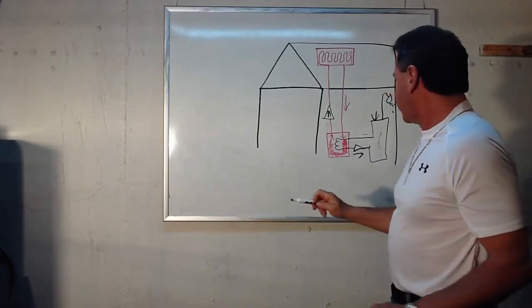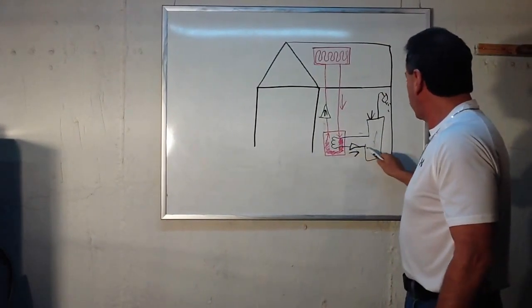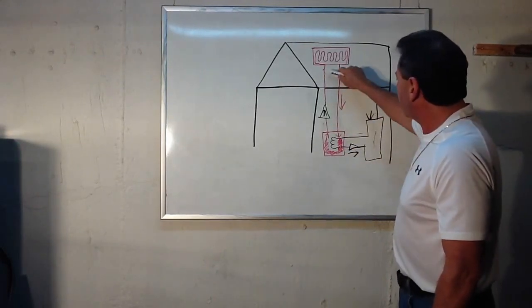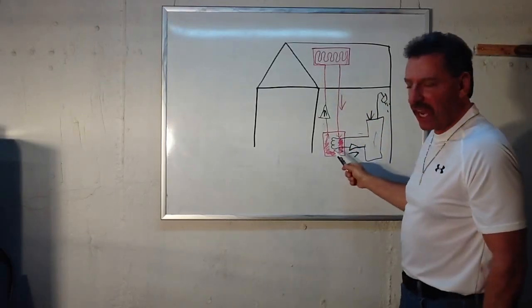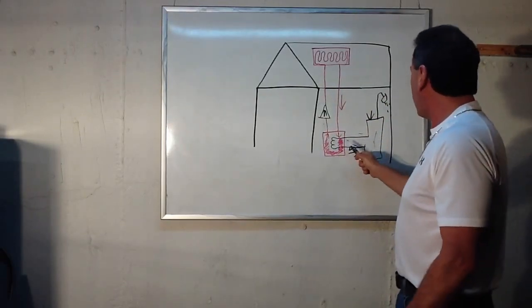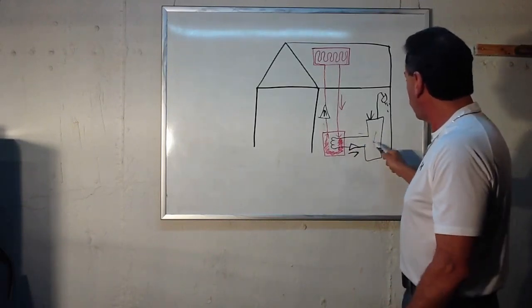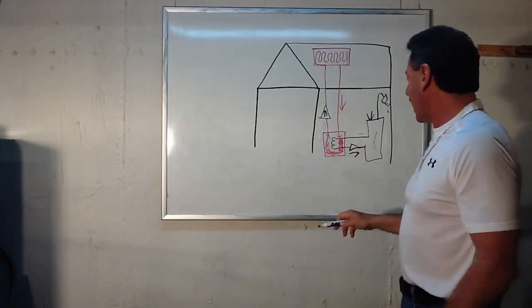So that's one way they get solar with a two pump system. One circulating the good clean water into an electric hot water heater and the other one's circling the glycol through what's called a heat exchanger. Where you get the hot water for free from the heat exchanger. The circulation being this way with the water. The circulation being this way with the glycol.